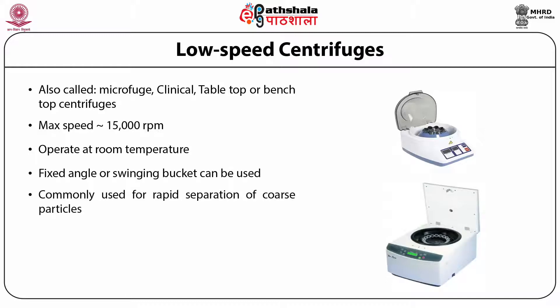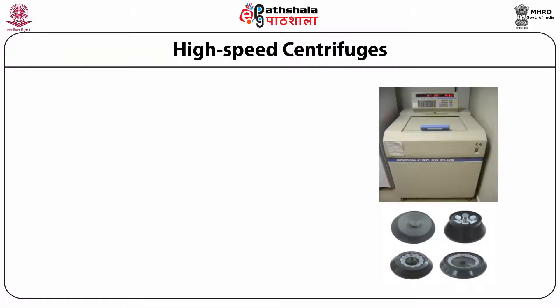The low speed centrifuge is also called a microfuge, clinical, or tabletop bench-top centrifuge. It operates at a maximum speed of 15,000 RPM, is most widely used in the laboratory, and operates at room temperature — this kind usually does not have a temperature control system. Both fixed angle and swinging bucket rotors can be used. It is commonly used for rapid separation of coarse particles like RBC from blood or DNA from protein. The sample is centrifuged until particles are tightly packed into a pellet at the bottom and the supernatant is separated.